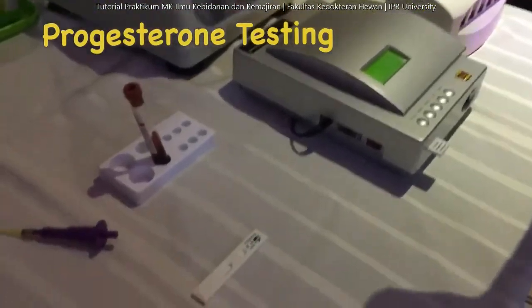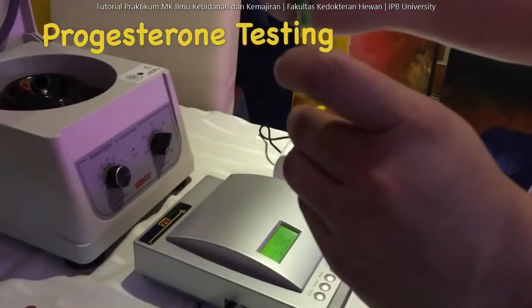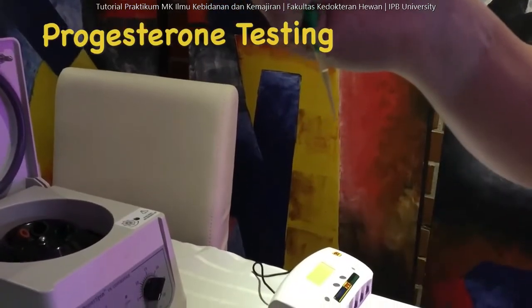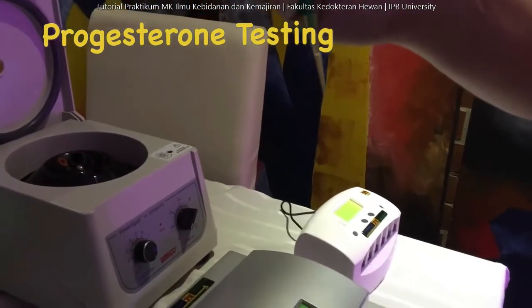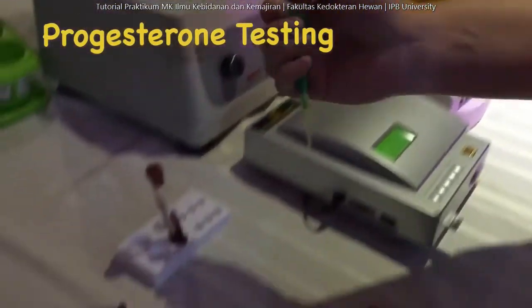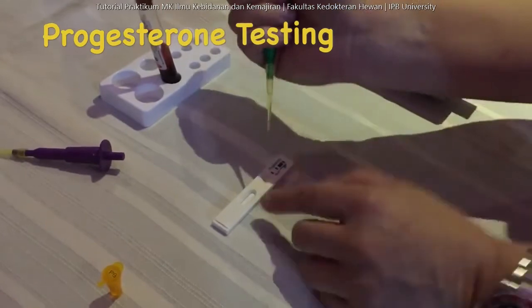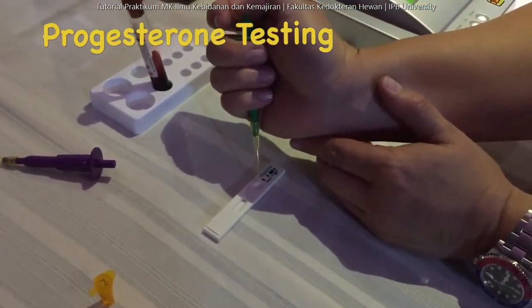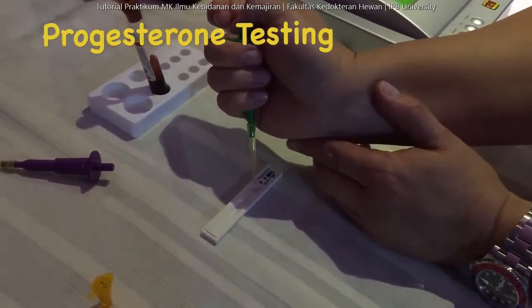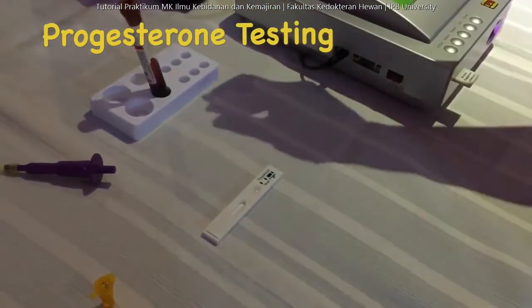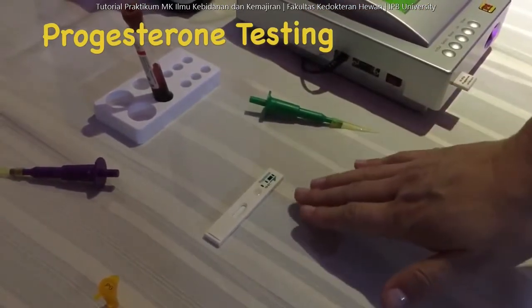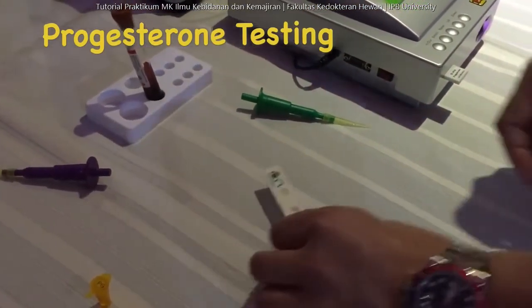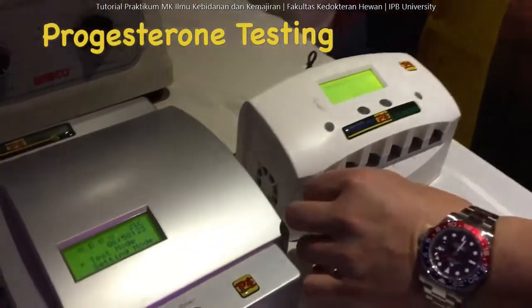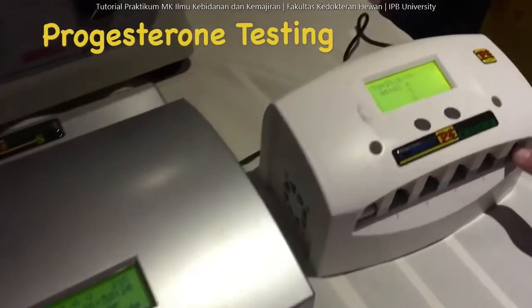Okay, so we have now a 75 µL pipette. You withdraw. Make sure there's no bubbles or breaks inside the buffer serum mix. And we want to put it in this little round hole right here. There's a long one and there's a little round one. We put it in the little round one very slowly. Make sure you don't spill anything. We wait until it drops a little bit, and we put it in the incubation chamber. The incubation chamber holds up to 6 tests at a time.